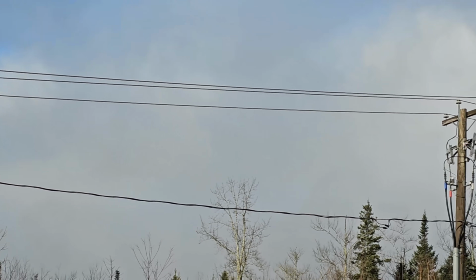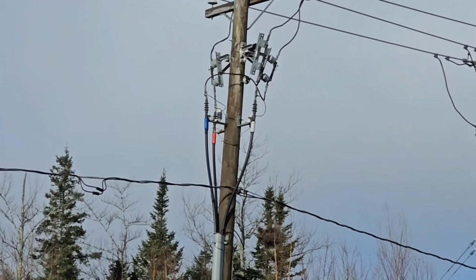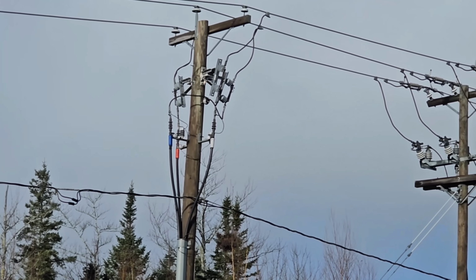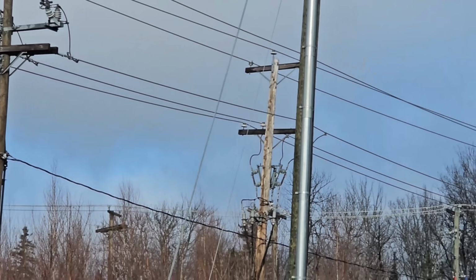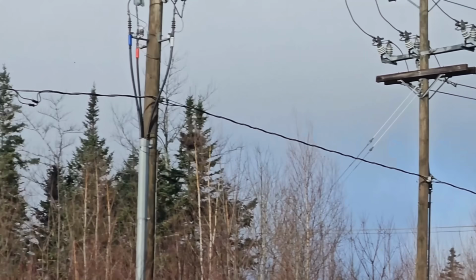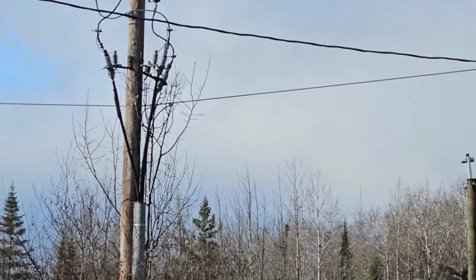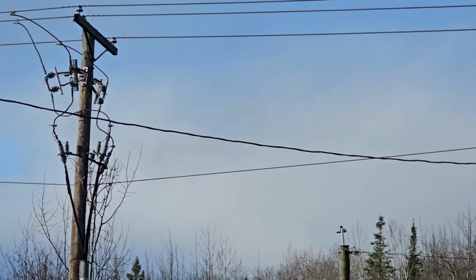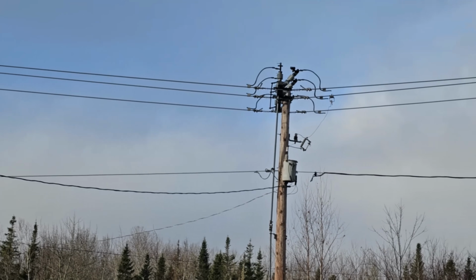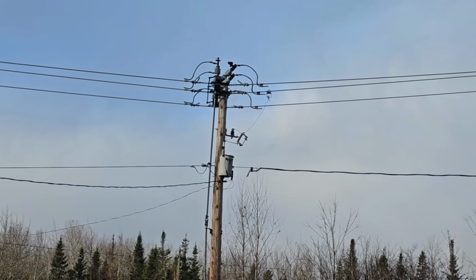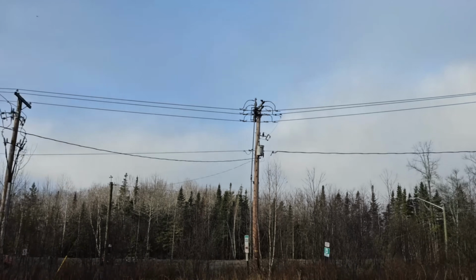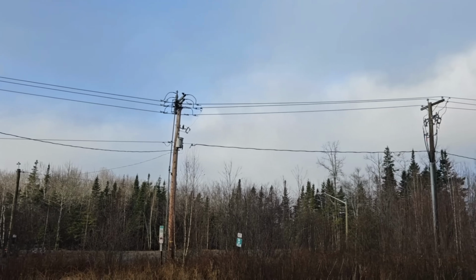However, you see these cables here coming out of the substation. That feeds, say, 500 customers. This one feeds 500 customers, this one feeds 500 customers. So when we're closing these switches in to pick up more customers, we can't simply just close the switch and pick up 1,500 customers in one shot.